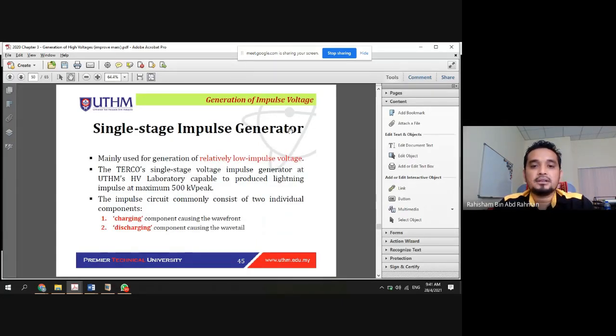Okay, for the single stage impulse generator, obviously a single stage, we are dealing with relatively low impulse voltage level, and this is the one that we have in the high voltage lab UTHM as well, and it is capable of producing lightning impulse at 500 kV peak. Okay, peak. So this is a single stage impulse generator. How are we going to obtain 1,000 kV, or 1 mega, 2 mega? The only way for us to obtain that value is by using the multi-stage impulse generator or cascaded version of the transformer. Alright, so then only we can achieve that.